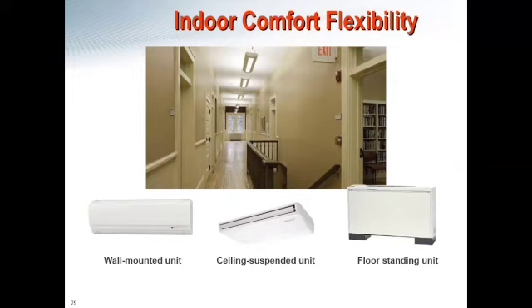Then moving to the right, we have the ceiling suspended unit. This is a very common type of VRF unit that you're going to see. It is very similar to your wall-mounted unit, the only difference being a slightly larger fan, which allows for a significantly further air throw to a space. It's really application specific when you might be seeing these. I see these a lot in restaurants and bars. But the main thing to take away from a unit like that is the air throw that you're going to be able to provide.